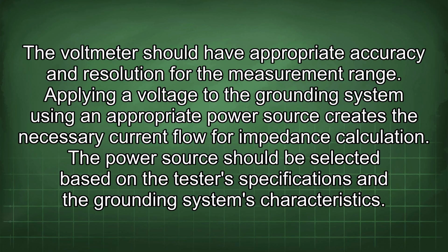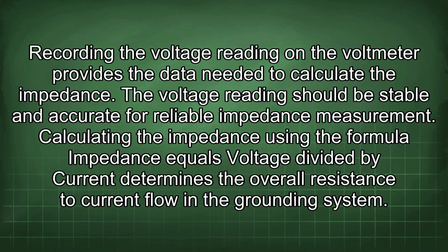Applying a voltage to the grounding system using an appropriate power source creates the necessary current flow for impedance calculation. The power source should be selected based on the tester's specifications and the grounding system's characteristics. Recording the voltage reading on the voltmeter provides the data needed to calculate the impedance. The voltage reading should be stable and accurate for reliable impedance measurement.